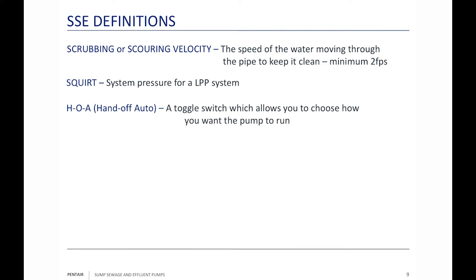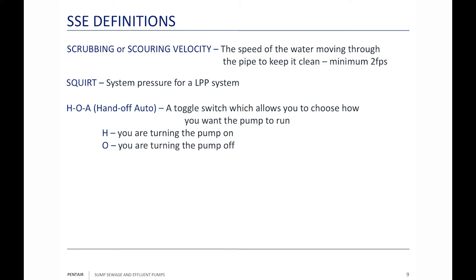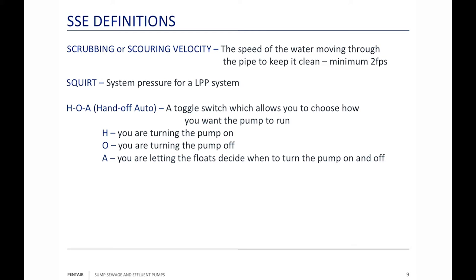HOA stands for Hand Off Auto — a toggle switch built into a control panel used to test the pump. Hand means I'm going to turn the pump on manually; I'm not letting the automatic system do that, which also means I have to turn it off. Off means I'm turning it off. Auto means I'm allowing the float system to decide when to turn the pump on and off.